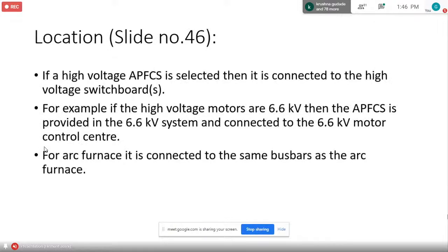Location. If a high voltage power factor correction system is selected, then it is connected to the high voltage switchboard. For example, if the system is 6.6 kV, then the APFC is provided in the 6.6 kV system and connected to the 6.6 kV motor control center. For an arc furnace, it is connected to the same bus bar as the arc furnace.